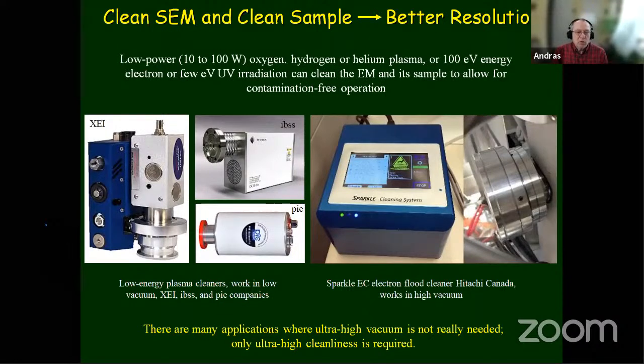This is called Sparkle EC, which uses an electron flood. So you can see the little control unit, that blue box, and the head, which essentially is a tungsten filament that emits low energy electrons and cleans the instrument over time, and also cleans the sample surface. As you saw, electron irradiation has a cleaning effect. So this is a lot more powerful than just this small few 10 picoamp electron beam.